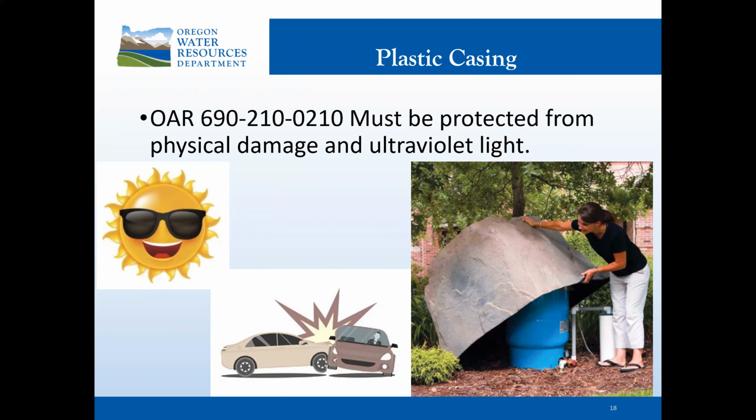And again, when using plastic casing, there's nothing that prevents pitless adapters from being used, but we recommend that they're not installed. And if they are, there needs to be extra care taken that the weight of the pump doesn't exceed the strength of the PVC or plastic casing.